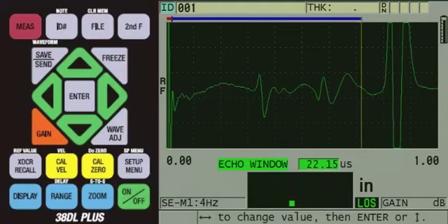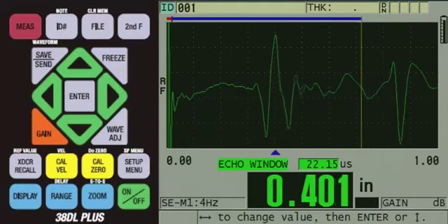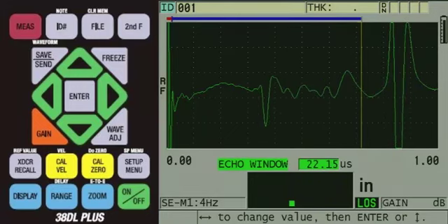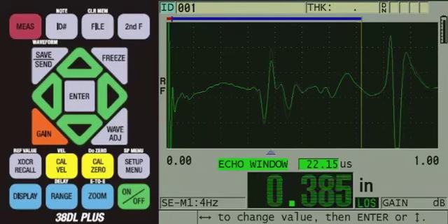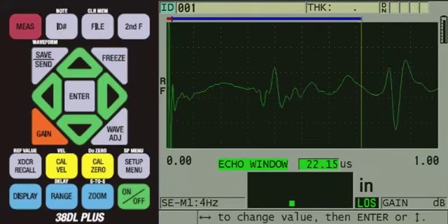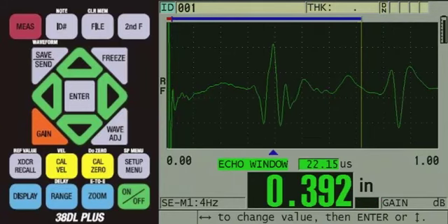As always, once the correct echoes are being detected and the thickness readings are close to what they should be, the next step would be to calibrate using samples of known thickness of the same material you are measuring and then save the transducer setup.